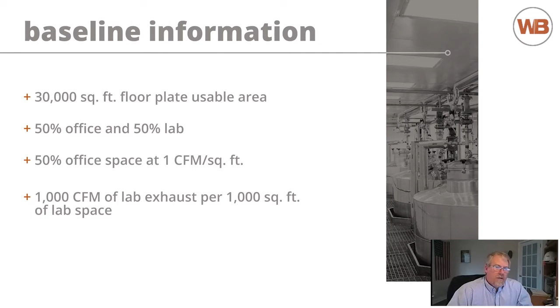So I wanted to give you guys a comparison between an all airside solution and a waterside solution. I'll start at the top with the idea that if you have 50% lab and an airside solution, you're going to need roughly 2 CFM a square foot. That airside solution at 2 CFM a square foot is going to provide roughly 1 CFM a square foot of 100% outside air makeup to support the lab exhaust requirement. The additional 1 CFM a square foot would be provided for the sensible cooling needs of that space.